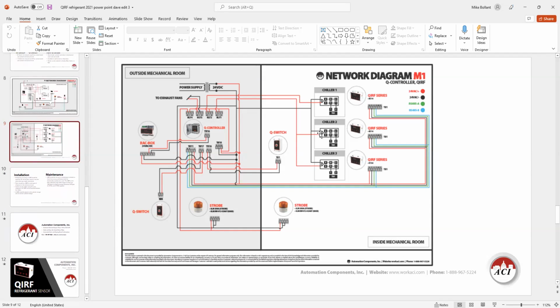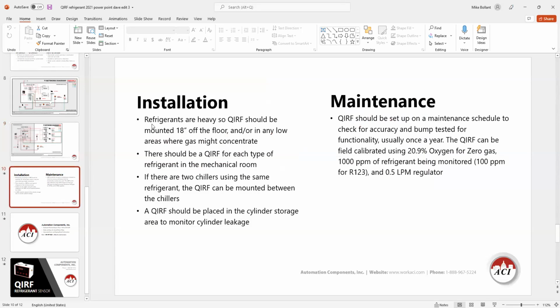Does this diagram make sense as well? Seems pretty cut and dry. Yeah, and the relays, whether it's the M switch or Q switch, are tied into the exhaust fans in the mechanical room. So if something happens, they hit the switch, it overrides, and you know how that sequence of operation works. For installation, we also recommend you mount the QIRFs about 18 inches off the floor. I think that's pretty standard.